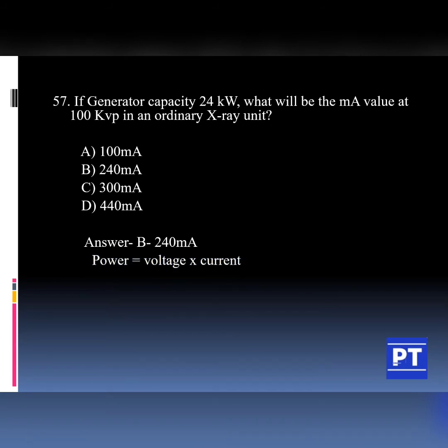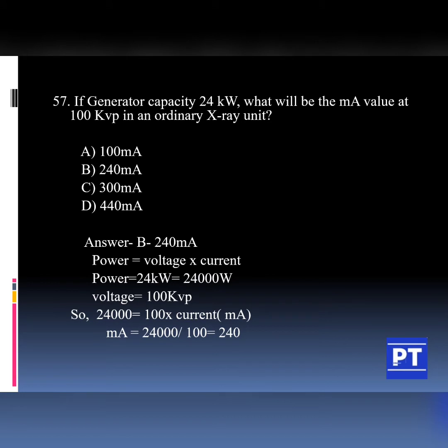Options are: Option A 100 mA, Option B 240 mA, Option C 300 mA, and Option D 440 mA. The answer is Option B, 240 mA. It can be calculated from the equation: Power equals voltage into current. Here the power is 24 kW, which converts to 24,000 watts, and the voltage is 100 kVp. Using this equation, we get the current MA as 240.